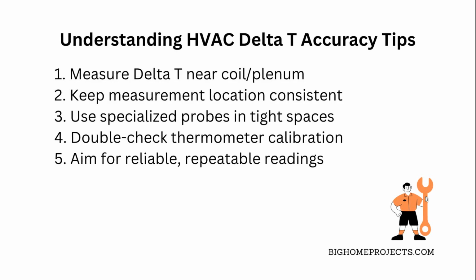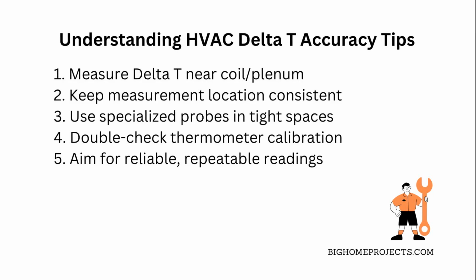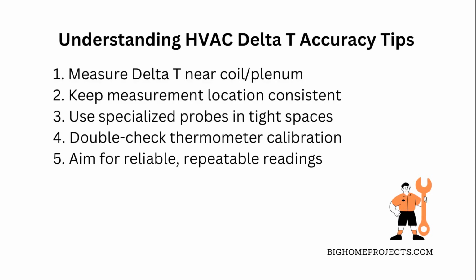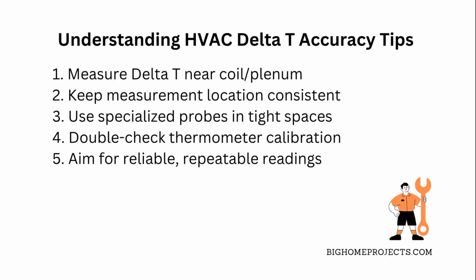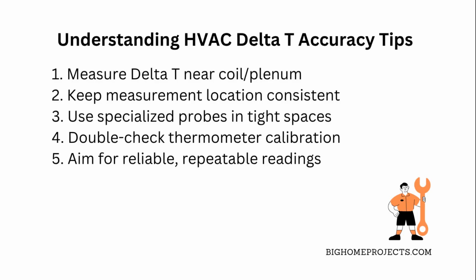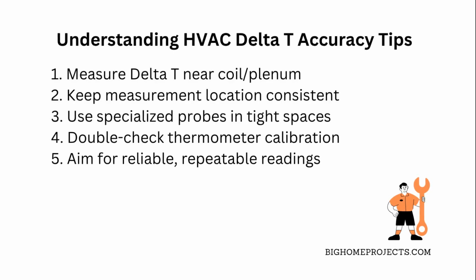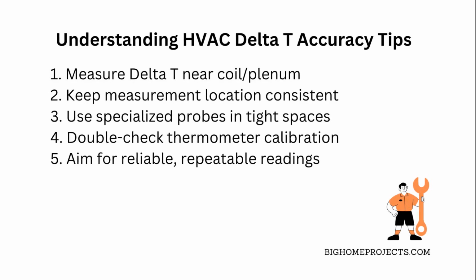It also helps if you keep your measuring spot consistent every time you check, so you can trust how your HVAC system is performing. And if you're stuck in a tight install where space is limited, maybe use specialized probes or tools designed for small spots. Don't forget to double-check your thermometer's calibration too, because even a tiny error there can skew Delta T results. The goal is to get reliable, repeatable readings so you know your system's running like it should without guessing.